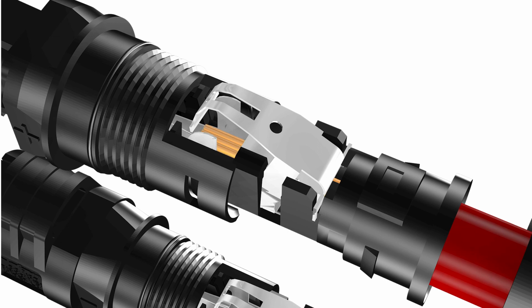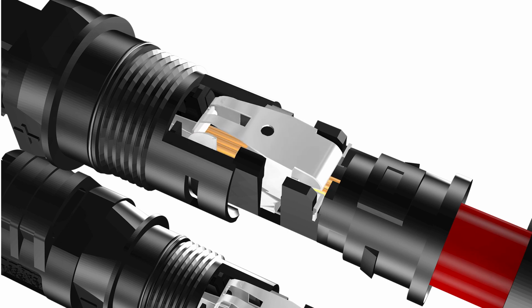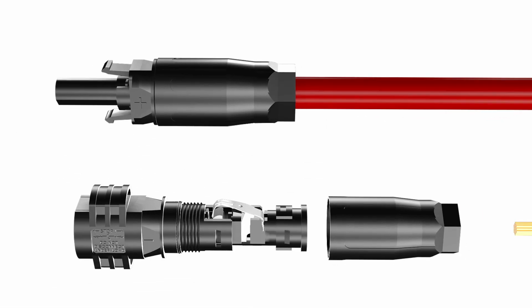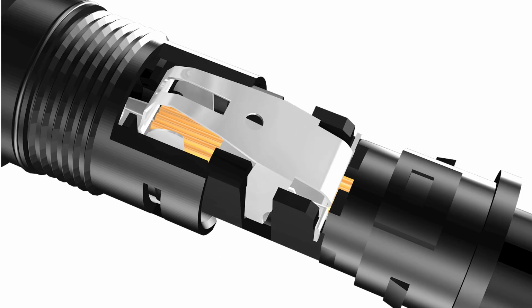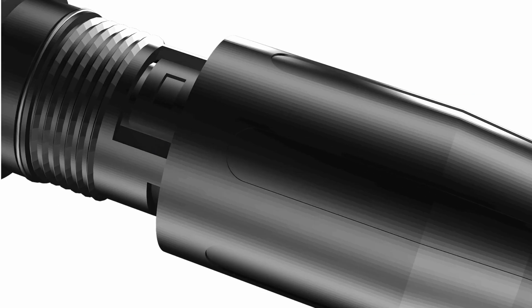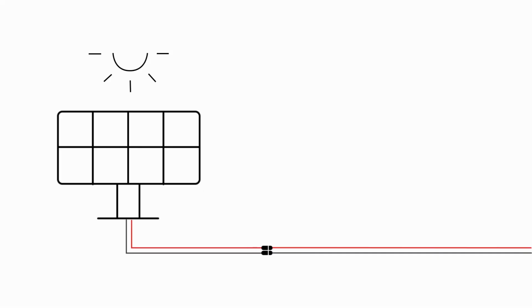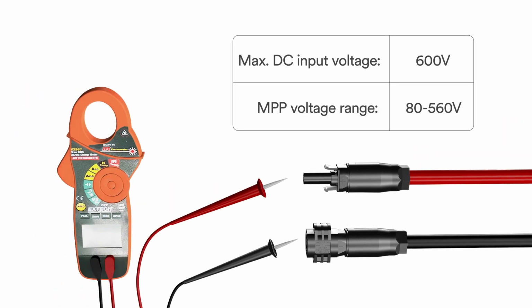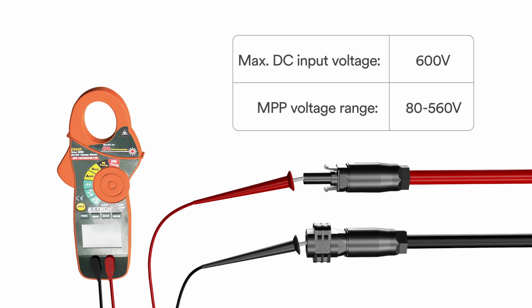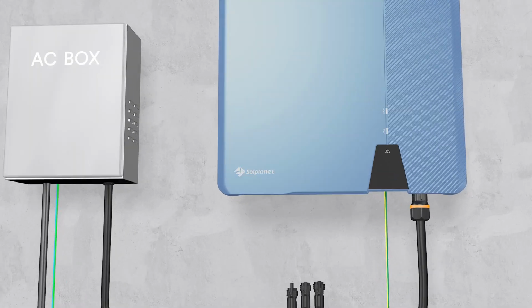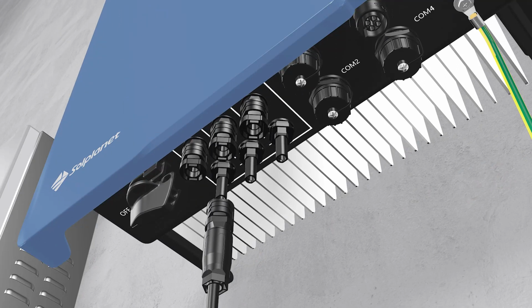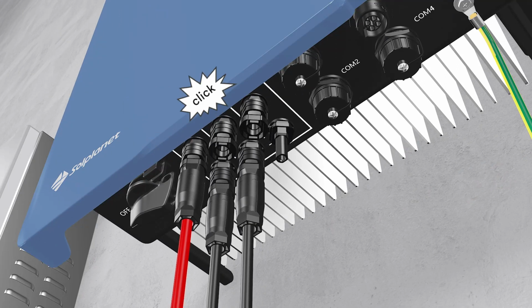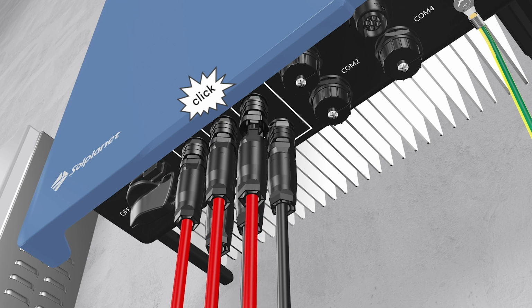Press the clamping bracket down until it audibly snaps into place. Ensure that the cable is correctly positioned. Push the swivel nut up to the thread and tighten. Connecting the PV array. Check whether the DC connector has the correct polarity. Ensure that the open circuit voltage of the PV array does not exceed the maximum DC input voltage of the inverter. Connect the assembled DC connectors to the inverter until they audibly snap into place. Ensure that all DC connectors are securely in place.